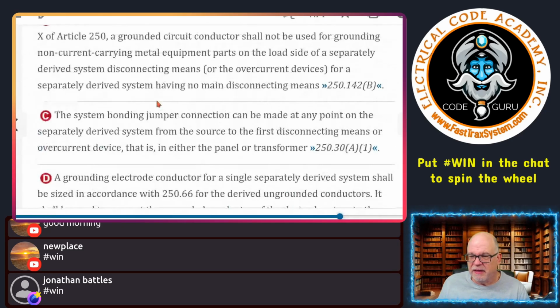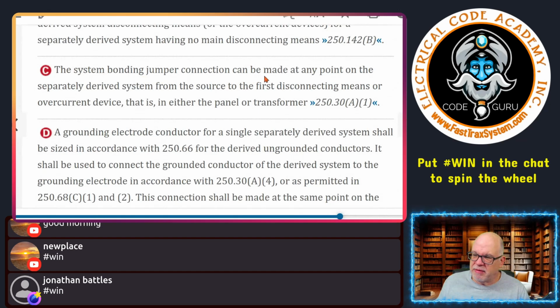It says the system bonding jumper connection can be made at any point on the separately derived system from the source to the first disconnecting means, or in our case, the overcurrent protective device in that first panel. This is in either the panel or the transformer. Okay, so that was the rule we talked about earlier. Not both, one or the other, because typically doing it in both could create problems, again, with objectionable currents, that type of scenario. So that's what we're doing. In this case, we chose to put it in the transformer, not in the panel in this example.